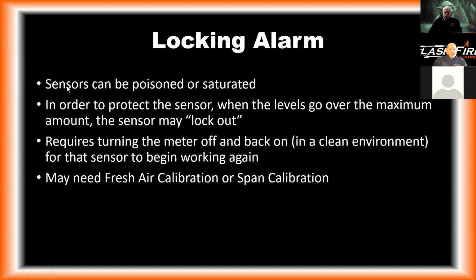Locking alarm. This is something that I have had departments run into with their Draeger meters. And basically what happens is you subject it to too much gas. And usually this happens in two scenarios. So what happens is the sensor says, oh my God, we went way too high here. I can't take any more gas in. So it basically locks out the sensor. What this does is saves the sensor's life so that it doesn't get completely saturated, destroyed, and needs to be replaced.